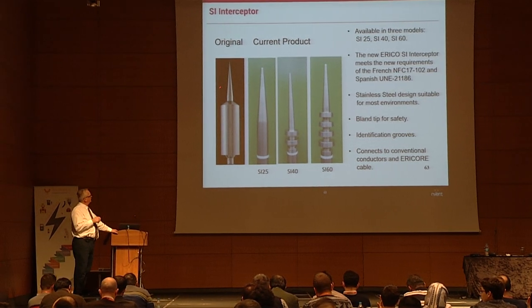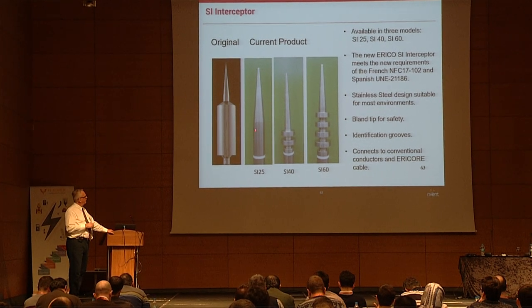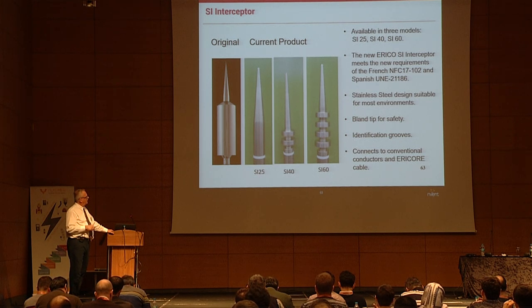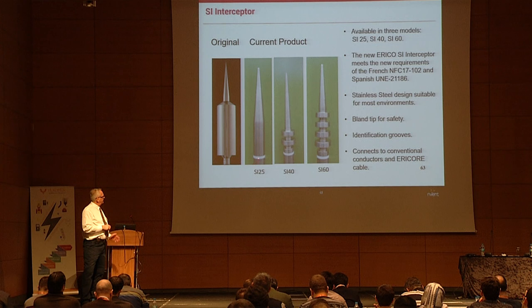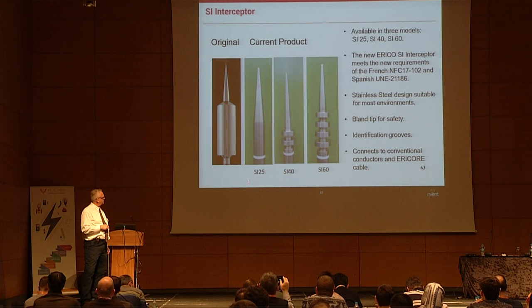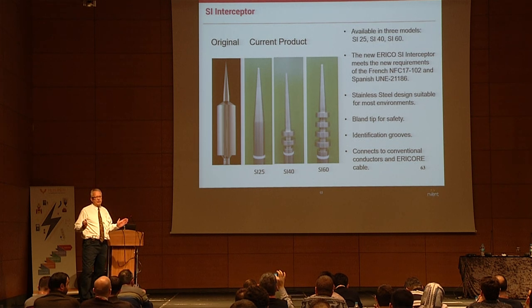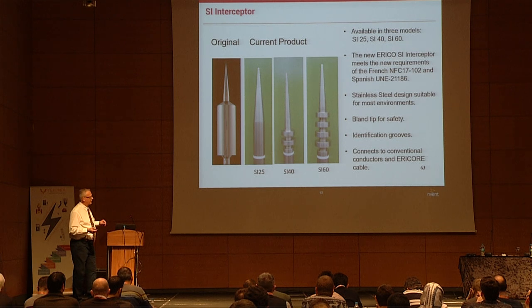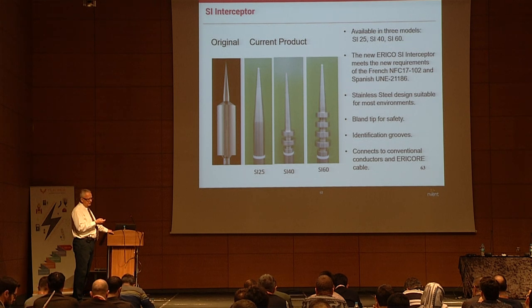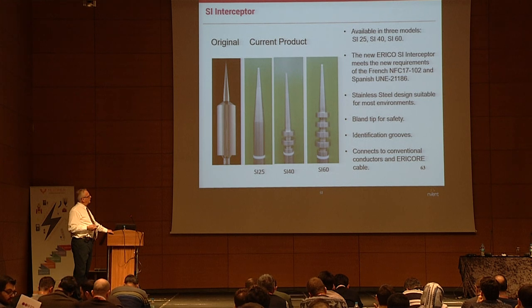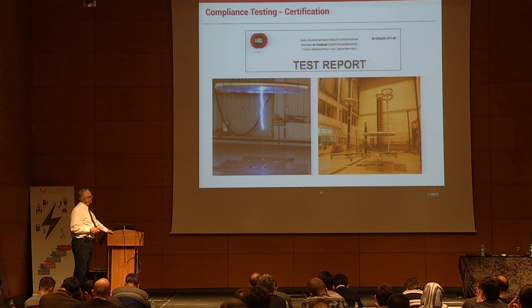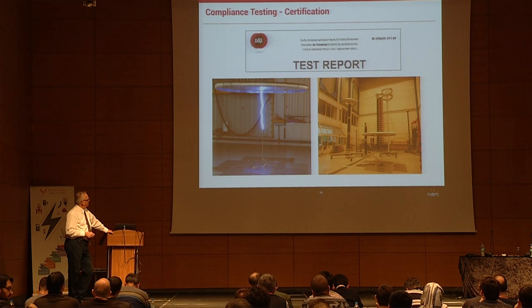Erico had the older style SI interceptor for the old standard. For the new standard we have SI 25, 40, and 60 models. The rings on the design distinguish the rating of the triggering system — SI 60 has four rings, another has two rings, and one has no rings — purely for the end user to identify the trigger mechanism rating. It's made from 316 stainless steel, environmentally durable, and has a full test report for performance.